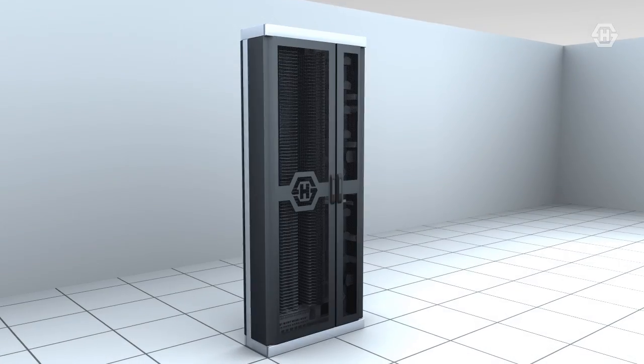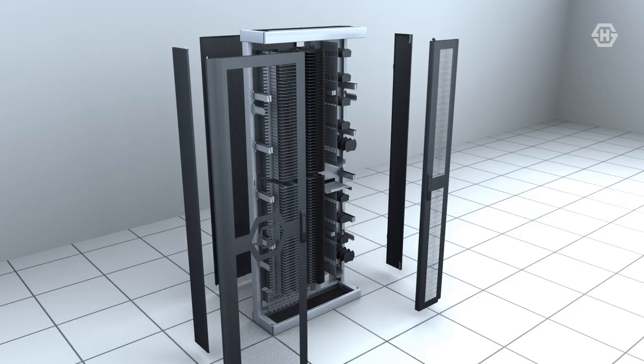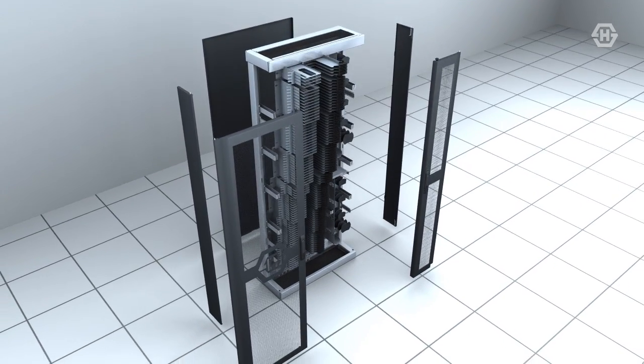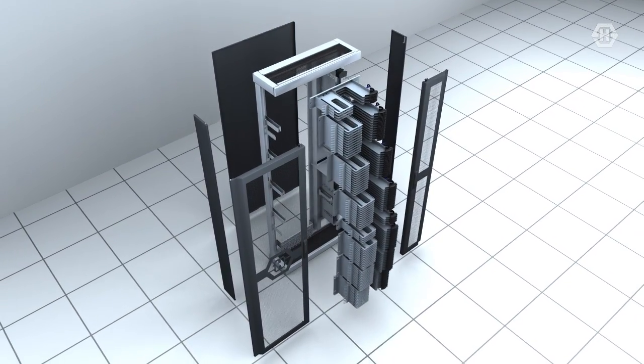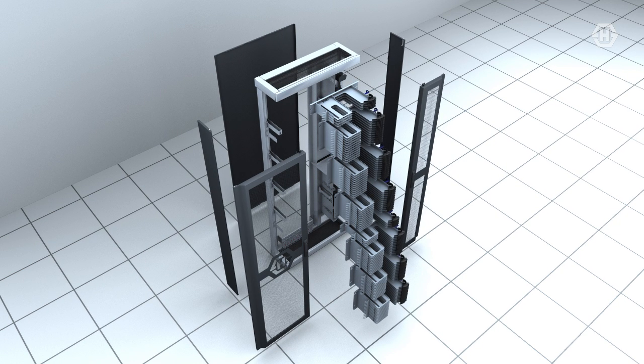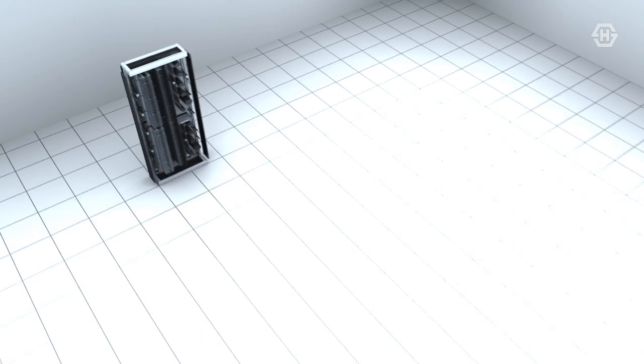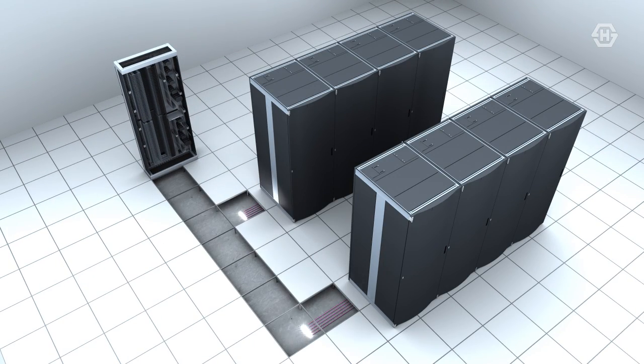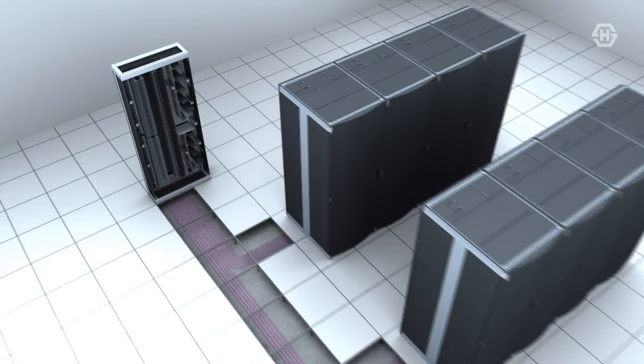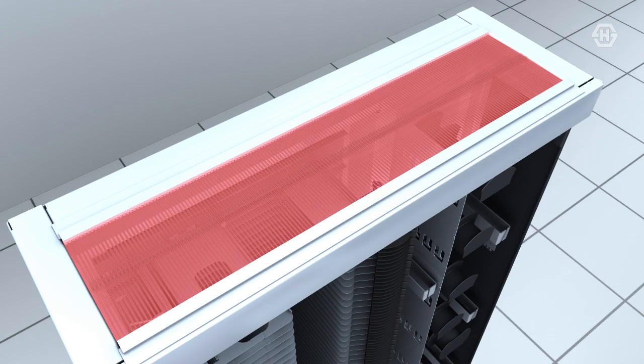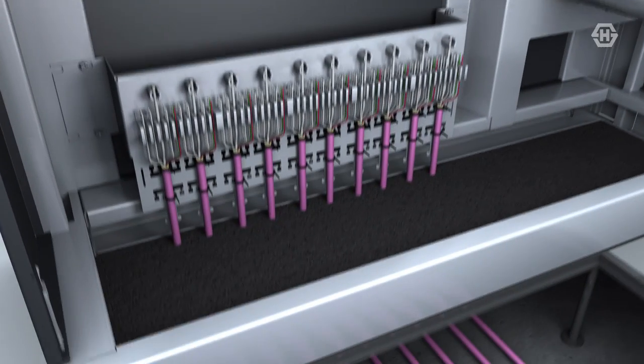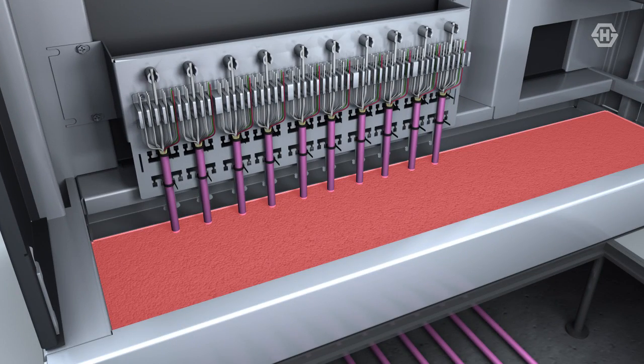If we strip out the internal elements of the Lisa NGR, we can see how Huber+Suhner's design competence and diverse practical experience has led to what we consider to be the most flexible and scalable fibre management system on the market. The large number of high-density cables entering the rack from different areas of the data centre pass through large apertures either at the bottom or the top of the rack. A full-length brush strip seals the rack in the upper position, and in the lower section, flexible baffles prevent contaminated air from entering the cabinet.